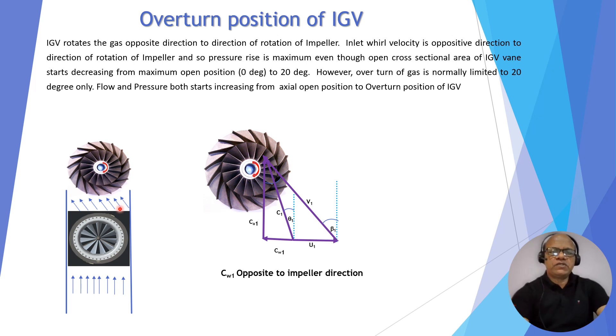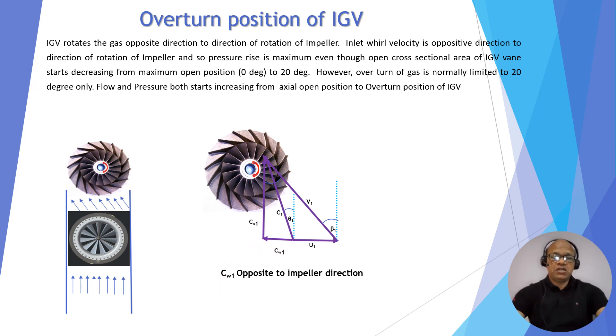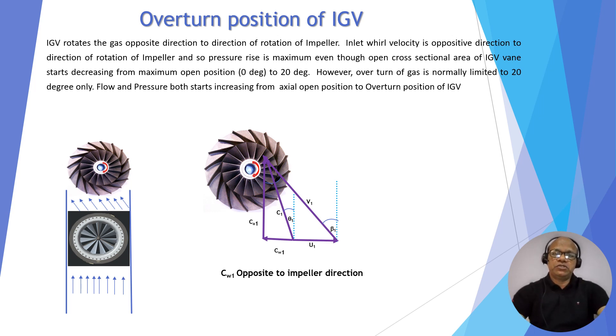You can see the velocity triangle for the overturned position: C1, U1, and V1. It has two components — CA1 in the axial direction and CW1 in the counter-rotation direction. The C1 position is opposite to the impeller rotation direction in the case of the overturned position of IGV.